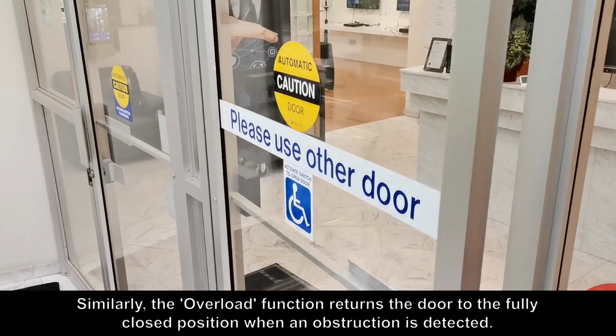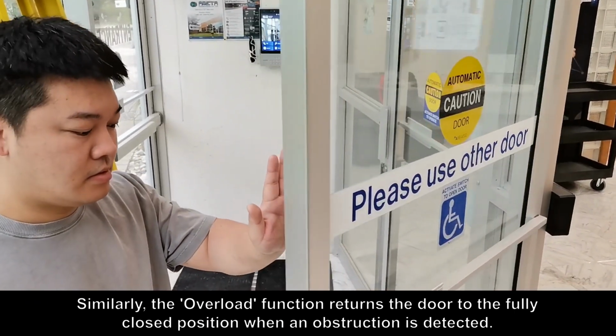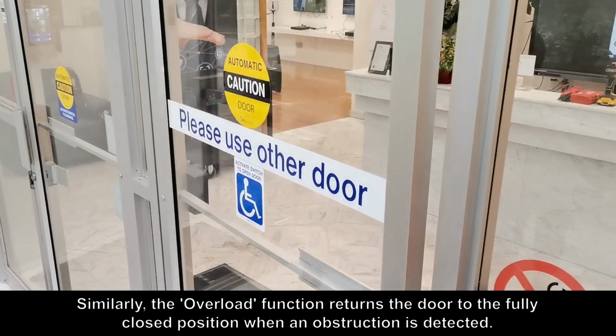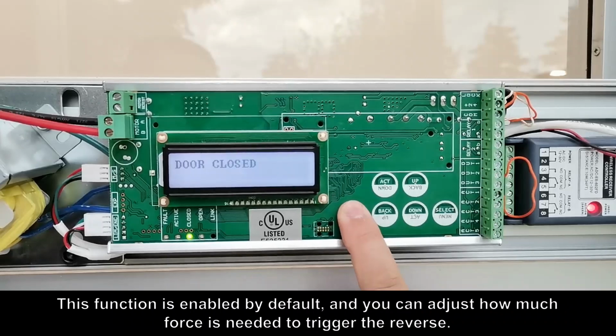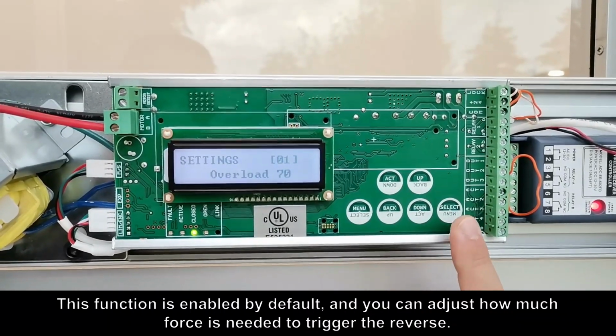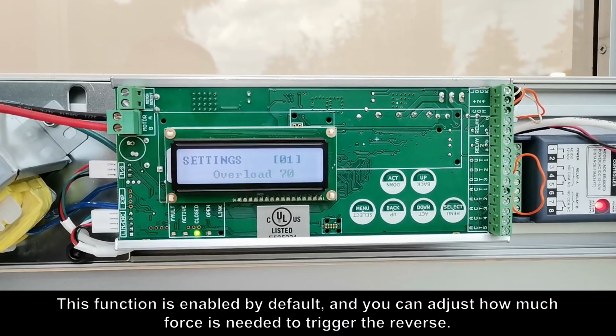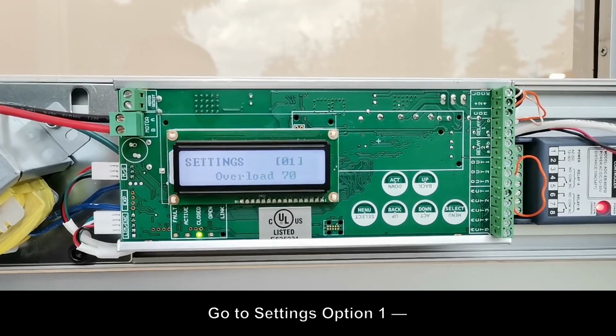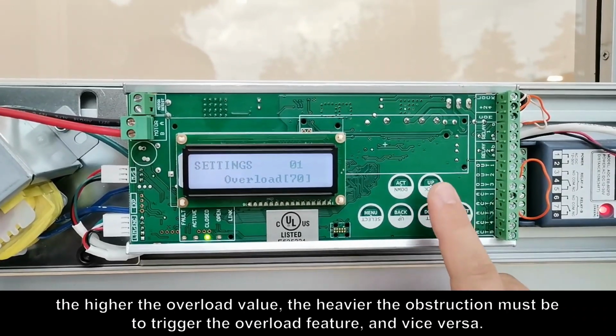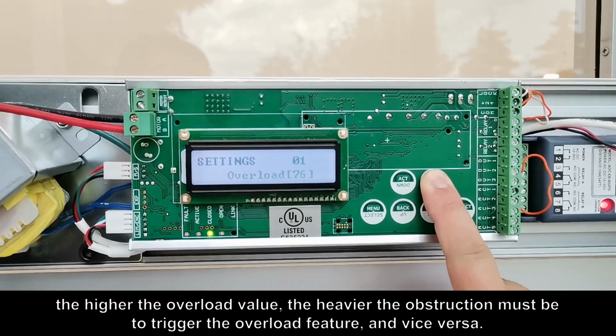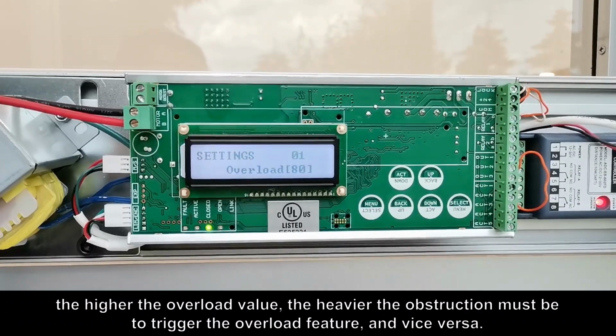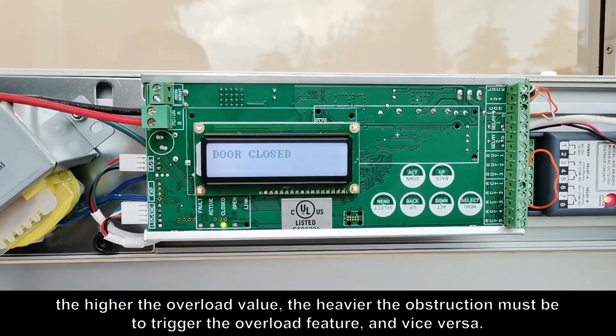Similarly, the overload function returns the door to the fully closed position when an obstruction is detected. This function is enabled by default, and you can adjust how much force is needed to trigger the reverse. Go to Settings option 1. The higher the overload value, the heavier the obstruction must be to trigger the overload feature, and vice versa.